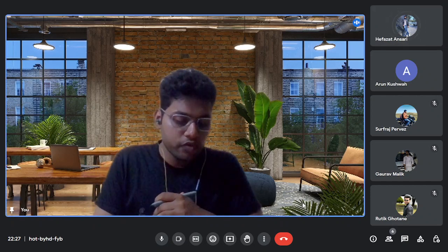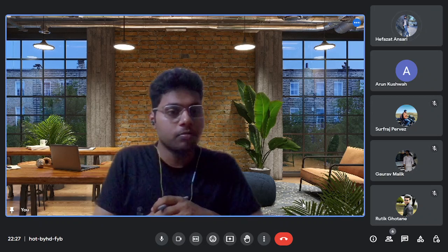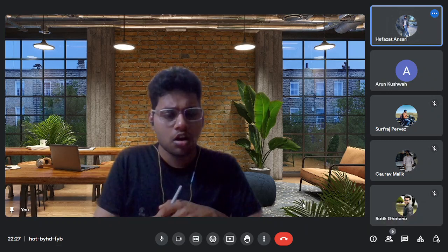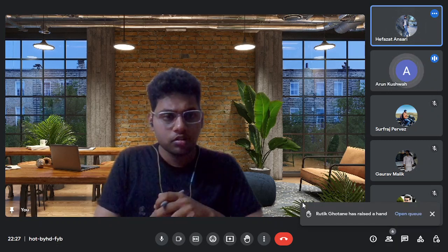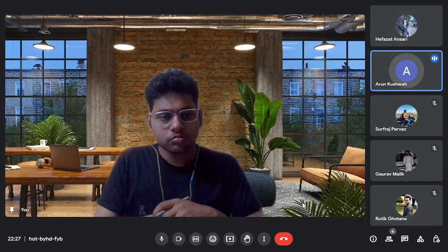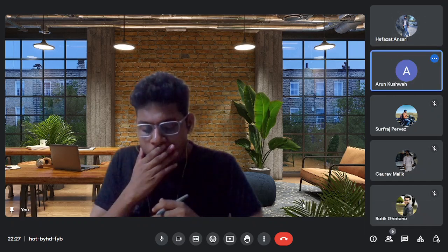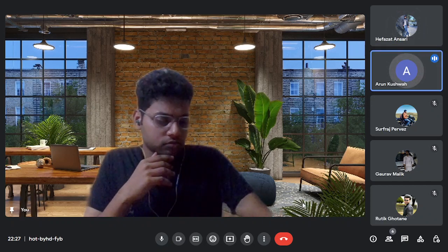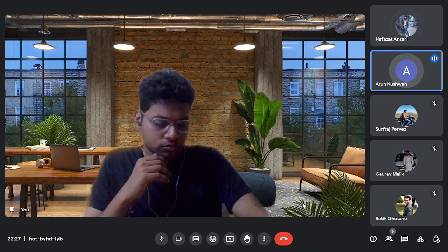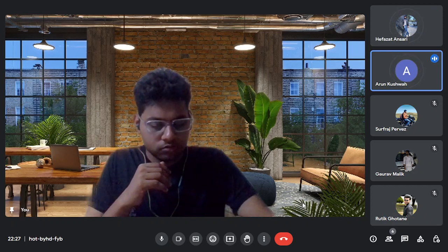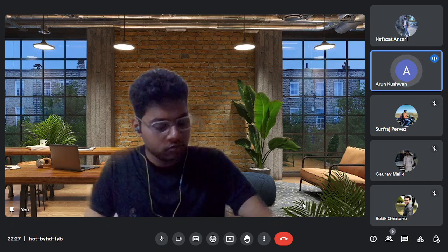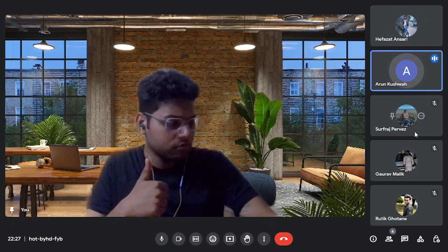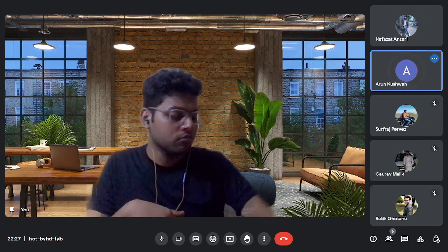Guys, why is there no relief valve fitted in a centrifugal pump? Yes, Arun. The centrifugal pump basically works at low pressure, and the designer kept this in mind. The supply lines and valves are designed so that they can sustain the pressure if the discharge valve is shut, as the pump works at 7 to 10 bar, which the discharge line and valves can sustain.